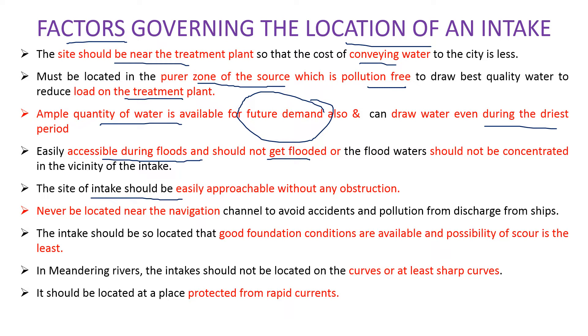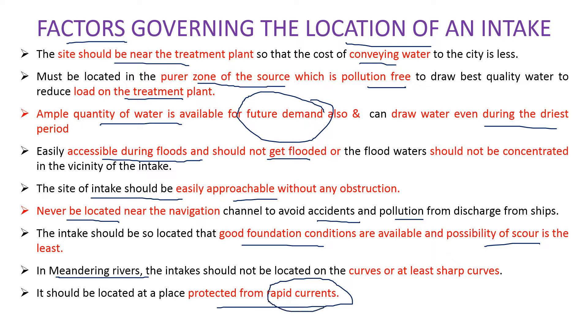The site of the Intake should be easily approachable for maintenance purposes. It should not be located near the navigation channel, as movement of ships creates chances of accidents and pollution. The Intake structure should be located where good foundation conditions are available to avoid the possibility of scour. Also, it should not be provided in a meandering river — one with very sharp curves — as these produce rapid currents that are dangerous to the structure.